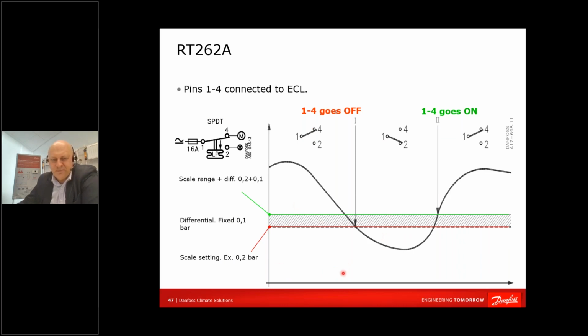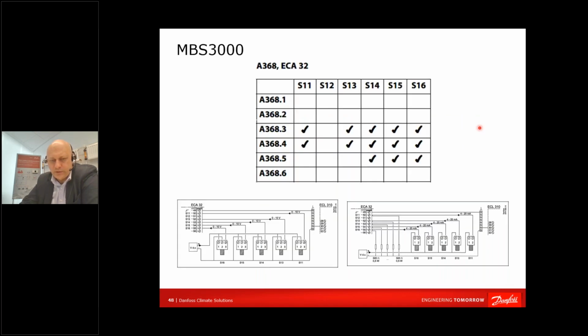So your scale setting, for example, 0.2 bar plus differential, which is fixed in this very differential pressure switch. When your pressure is falling down to the scale setting and below, changeover happens. When your pressure starts to build up to the scale setting plus differential, the contacts are returning. So that's how a pressure switch is working.